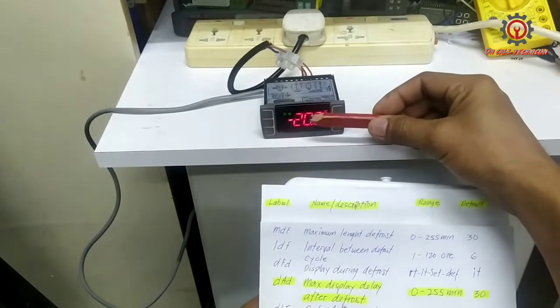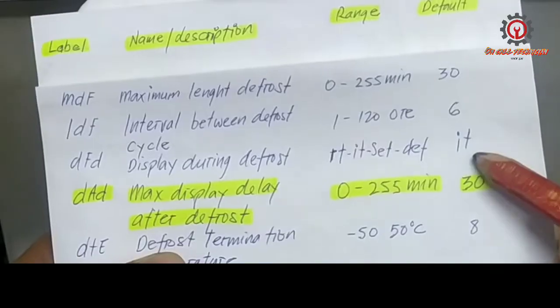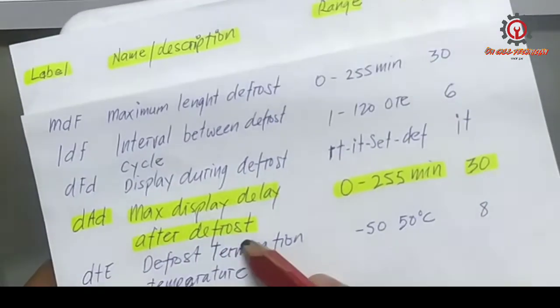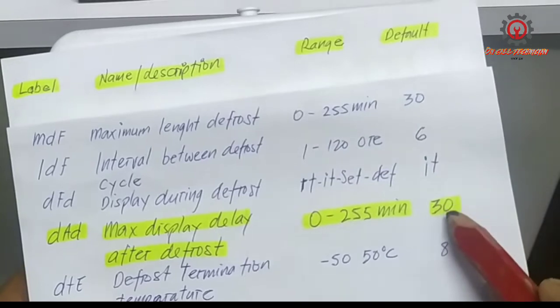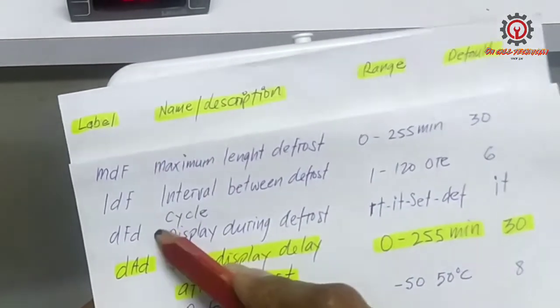IT is the display temperature at the start of defrost. The problem is the DAD - the maximum display delay after defrosting. I'm going to teach you the relevance of this DAD to IDF, MDF, DFD, and DTE.